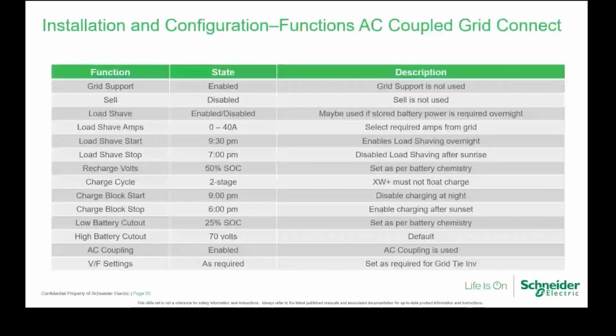We'll look at the configuration. When you're defining an AC coupled grid connection, grid support will be enabled. Sell is disabled. Low, because it doesn't really matter. You will have a sell, but the sell parameters will not actually do anything. You can enable load shaving. If you want, say, zero input from the grid at night time, you can then use your batteries if you've got enough storage there. Then you set up your load shave amps, then your load shave start and stop.